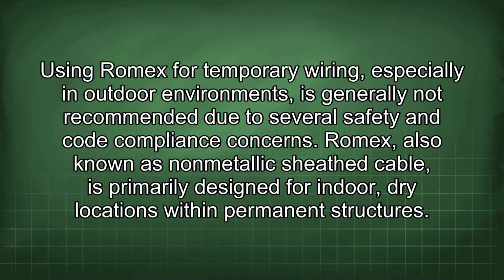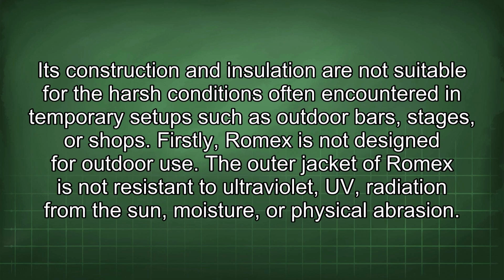Using Romex for temporary wiring, especially in outdoor environments, is generally not recommended due to several safety and code compliance concerns. Romex, also known as non-metallic sheathed cable, is primarily designed for indoor, dry locations within permanent structures. Its construction and insulation are not suitable for the harsh conditions often encountered in temporary setups such as outdoor bars, stages, or shops.